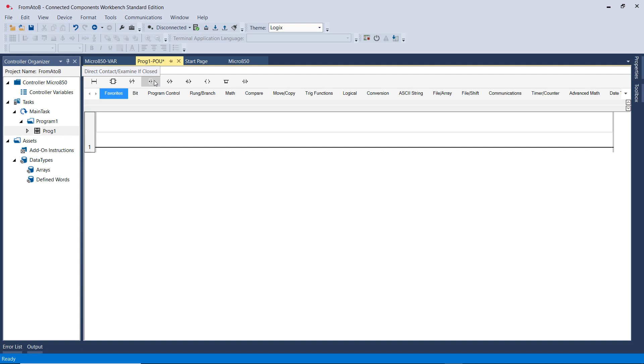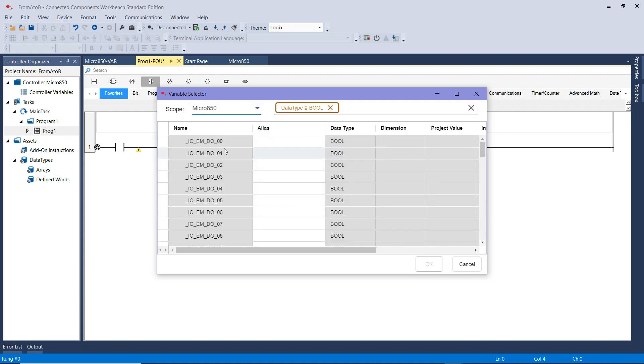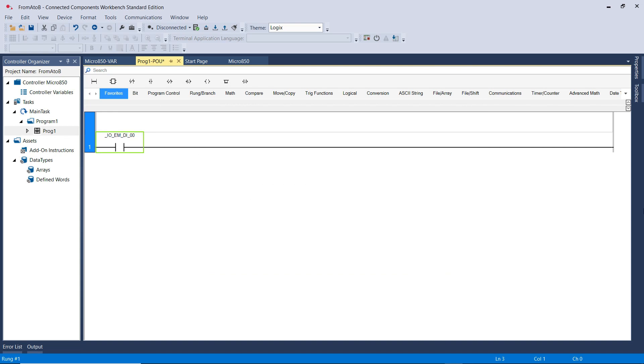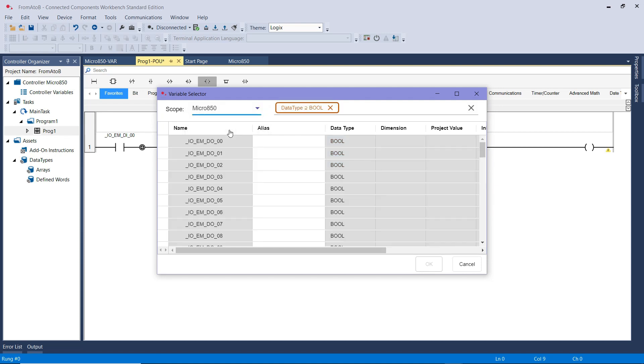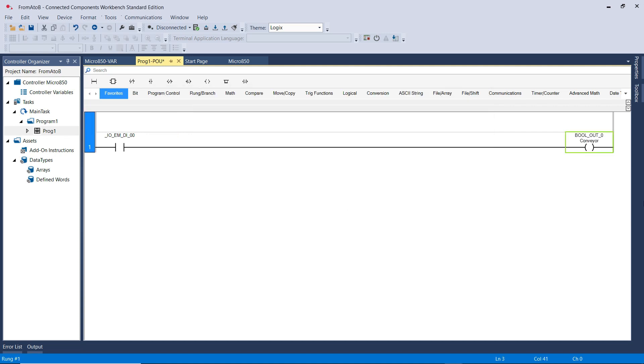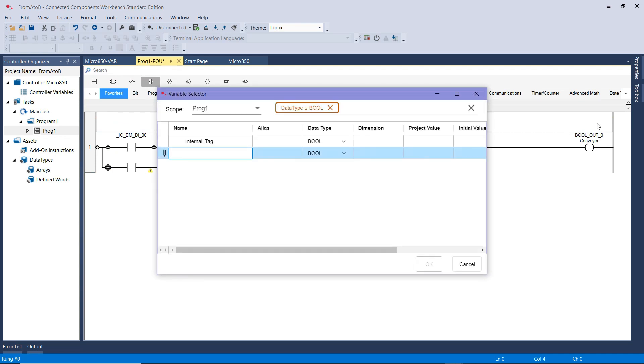Go ahead and grab an XIC instruction. Then from the variable selector, go here and select Micro 850, scroll down until you find the address for the input - the first one - double click, and you have it. Once I click on this, I want to activate the conveyor, so the conveyor is an output - drag it here. Then from the dropdown menu select Micro 850, and this time the conveyor is the address I added from FactoryIO, which is Boolean Out Zero, double click. Now to keep the conveyor running, I'm going to use a branch with an XIC instruction using the same address as the conveyor.